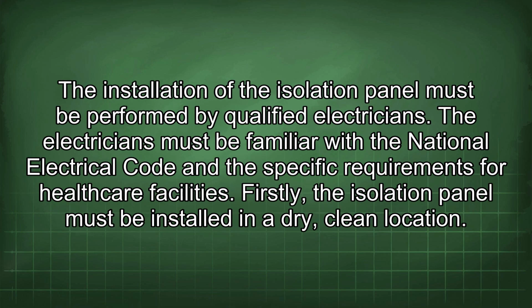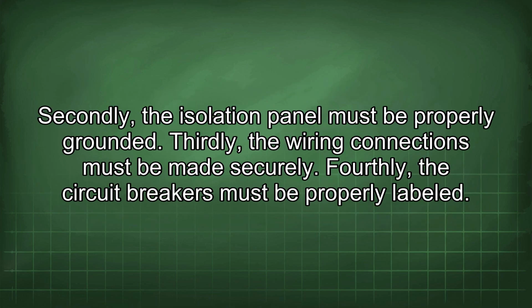The installation of the isolation panel must be performed by qualified electricians. The electricians must be familiar with the National Electrical Code and the specific requirements for healthcare facilities. Firstly, the isolation panel must be installed in a dry, clean location. Secondly, the isolation panel must be properly grounded. Thirdly, the wiring connections must be made securely.